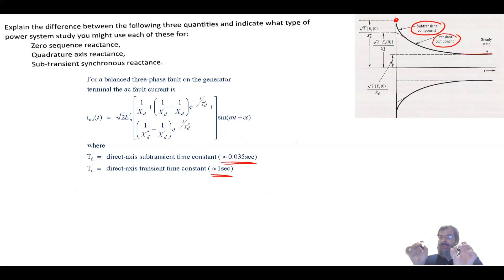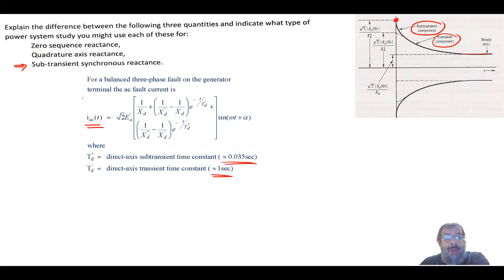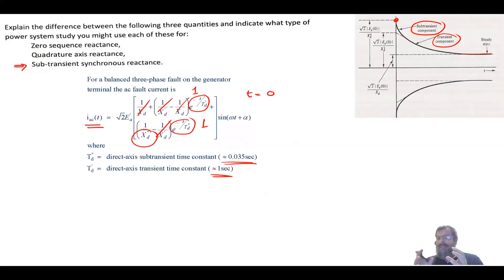In the sub-transient period, the current is very large, which means the dominant reactance limiting the current at the start of the fault is the sub-transient synchronous reactance. This is clearly shown in the fault current formula: at t=0, the exponential terms equal one, the other components cancel, and only one over xd double-prime (the sub-transient reactance) remains — this is the only reactance limiting the fault current at inception.